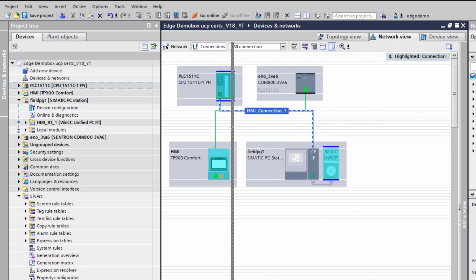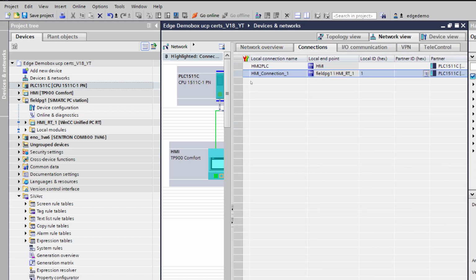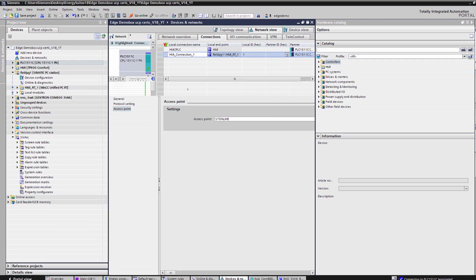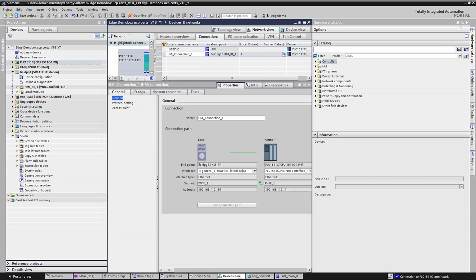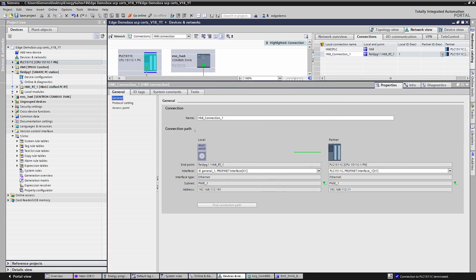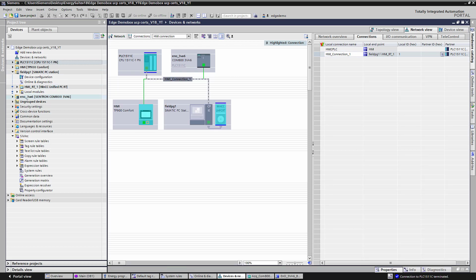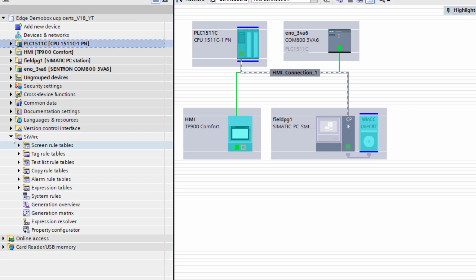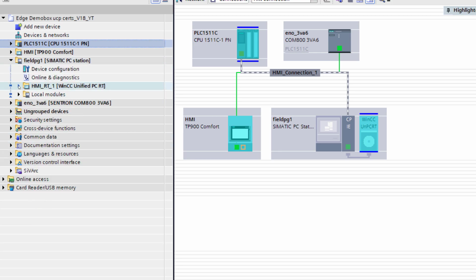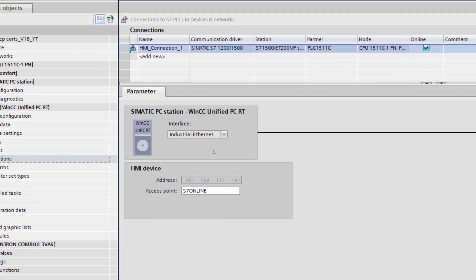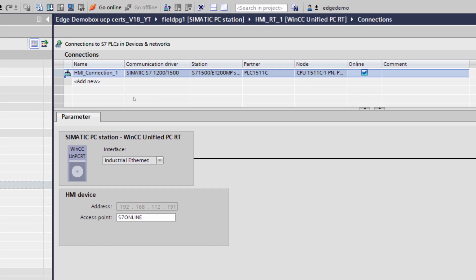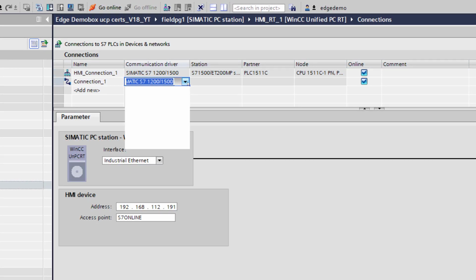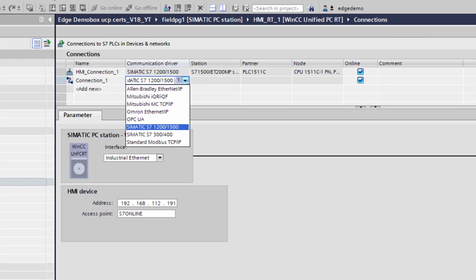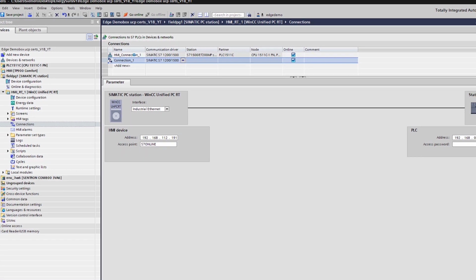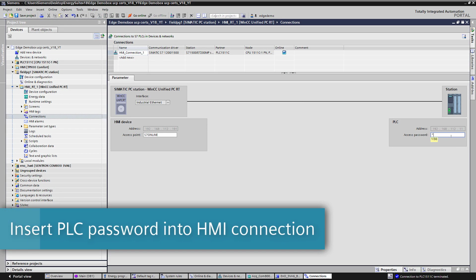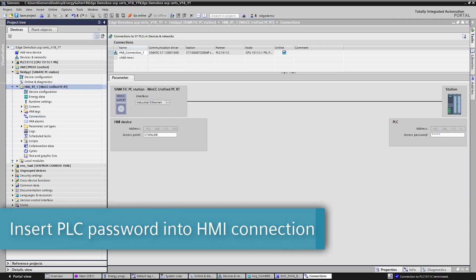The HMI connection can be found also in the Connections area, where you can investigate things like the properties, the exact same parameters and configurations can be adjusted in a similar way in this area. So going to the HMI and going to the runtime connections, it's really important to note the different options that we do have. The drop-down menu shows you the different communication drivers that are available for Unified PC Runtime. The last thing to do is to place the HMI Connection Password inside this field here.